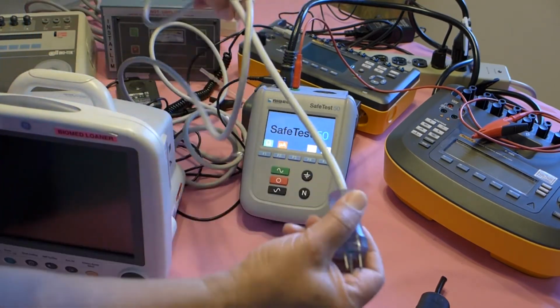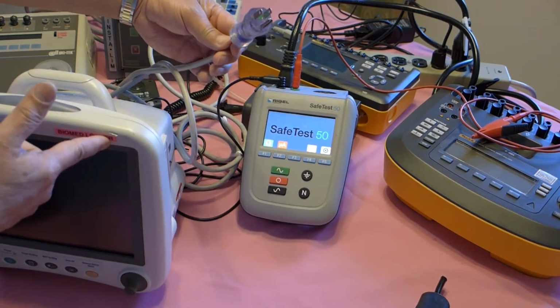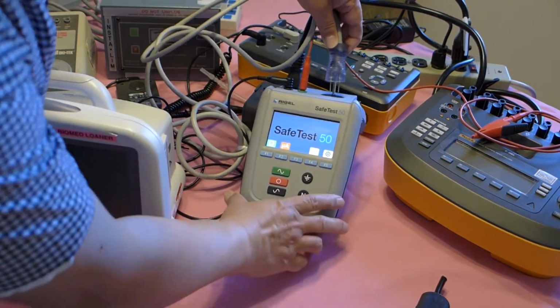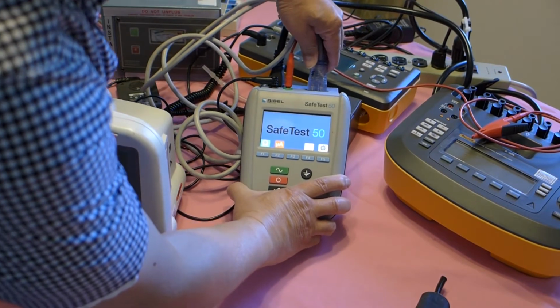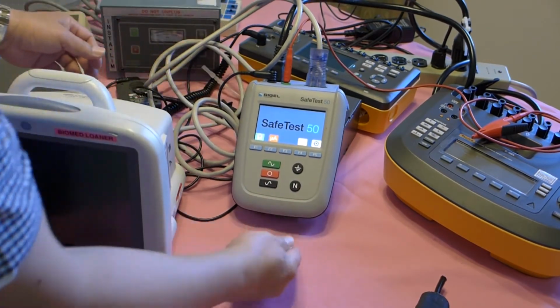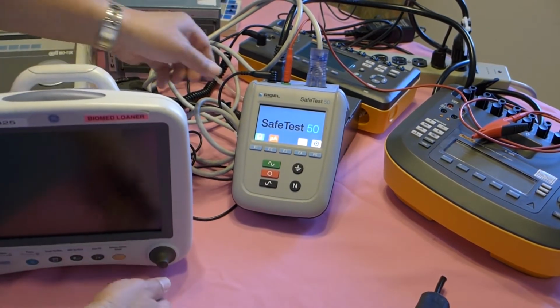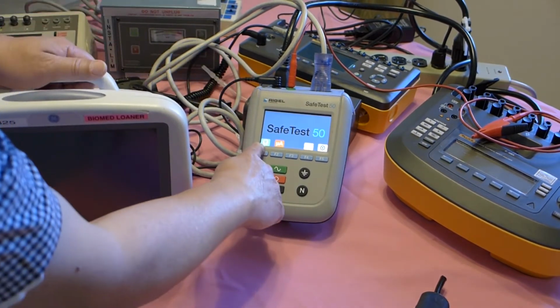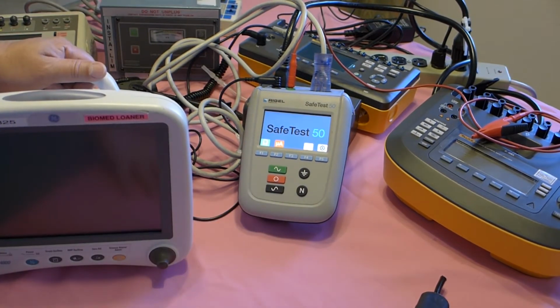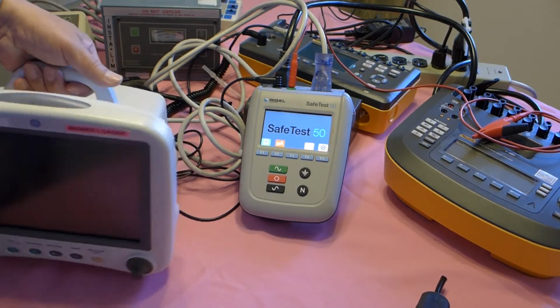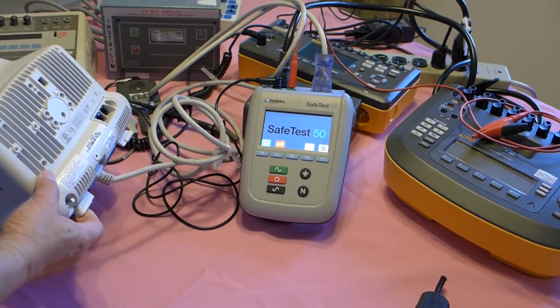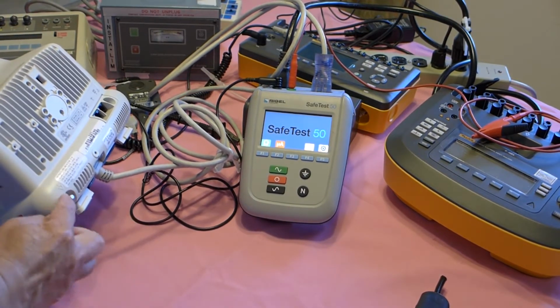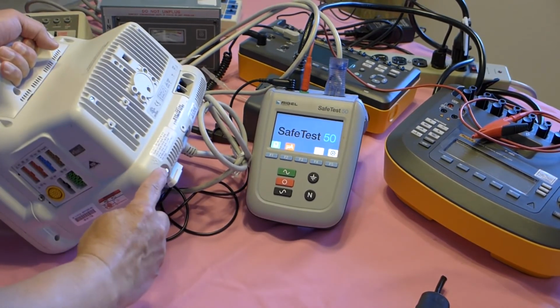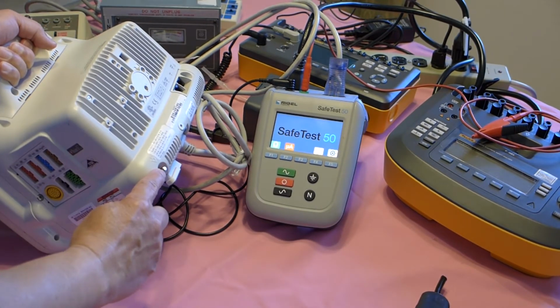We have to plug the power cord of the monitors into the receptacle on the safety analyzer. Then, to do the ground wire resistance, the standard for the ground wire resistance is about 0.5 ohms, or 500 milliohms. So we need to find, normally, the ground prongs of the medical device.